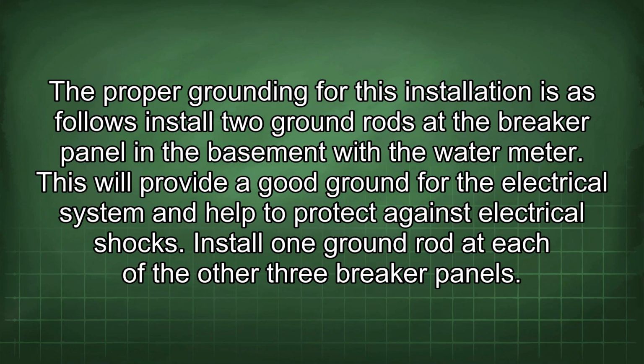Proper grounding for this installation is as follows. Install 2 ground rods at the breaker panel in the basement with the water meter. This will provide a good ground for the electrical system and help to protect against electrical shocks.